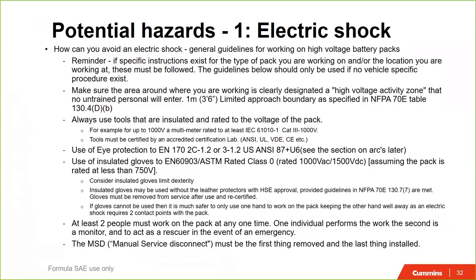You should always use insulated gloves with a leather gauntlet over the top. But at Cummins, we do permit that if this limits your dexterity too much for handling fasteners inside a battery, single-handed working is allowed. If you're working single-handed, there's not enough potential difference generally across the areas you're working to deliver a dangerous electric shock. But I would make sure you don't do that alone.